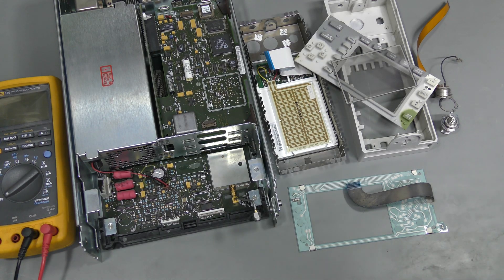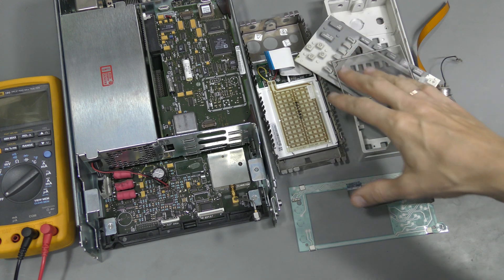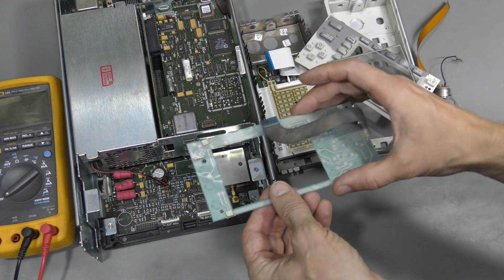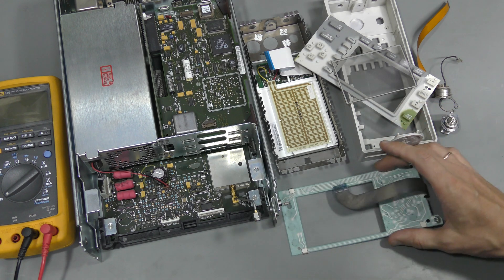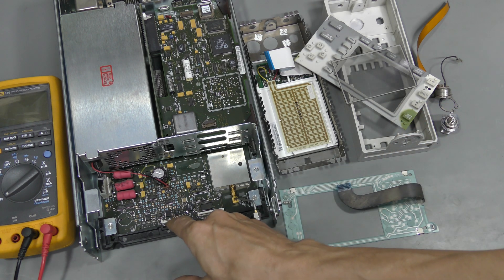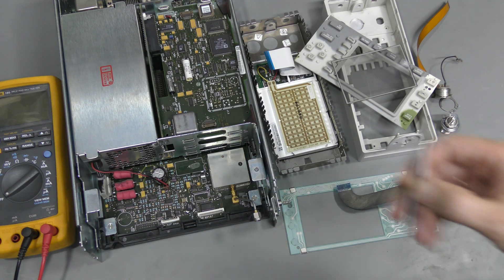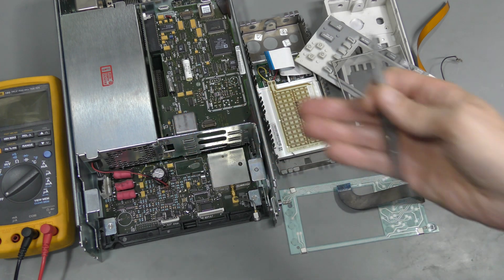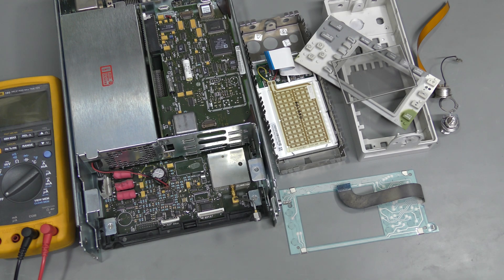I took the front panel apart, which was a bit tricky. And I traced connections to this power button. There are two separate lines going to this connector, pins 10 and 11 here. And there are two vias right next to the connector. And I shorted these two vias with tweezers. And the instrument powered up just fine.